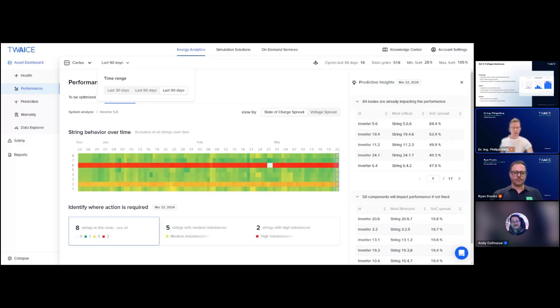So here we can see that especially when it comes to large imbalances and when single cells or modules drifted away for some reason, the BMS SoC usually really gets in trouble for LFP because of the flat OCV of all the cells. And this is where several downstream effects can happen.